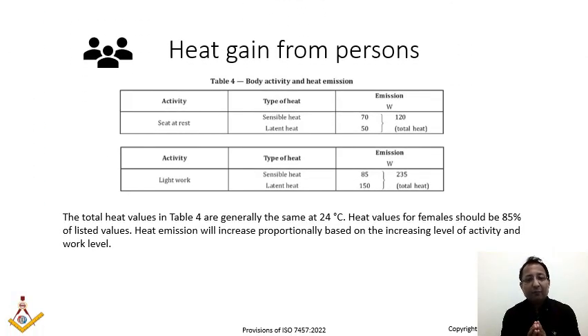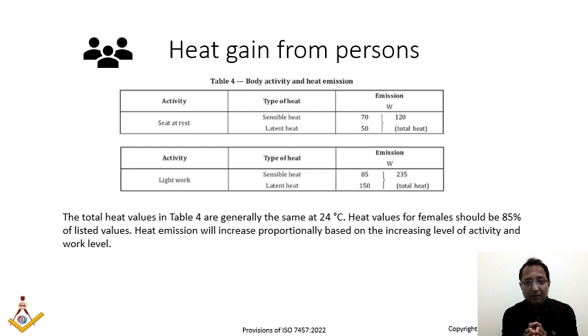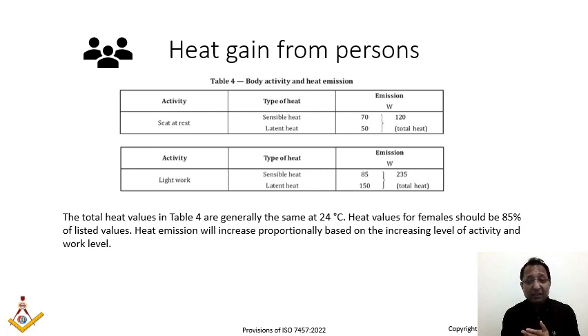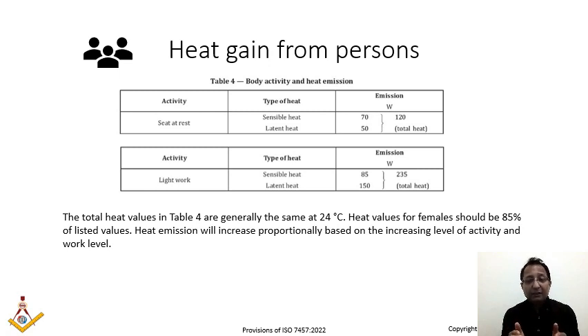This slide covers heat gain from persons per ISO 7457. The values are provided for seated at rest and light work, including sensible and latent heat components as used for HAP calculations. These values apply at 24°C design temperature — even if you design for 24°C they remain the same. Heat values for females should be taken as 85% of the listed values. Heat emission increases proportionately with increasing activity and work level.